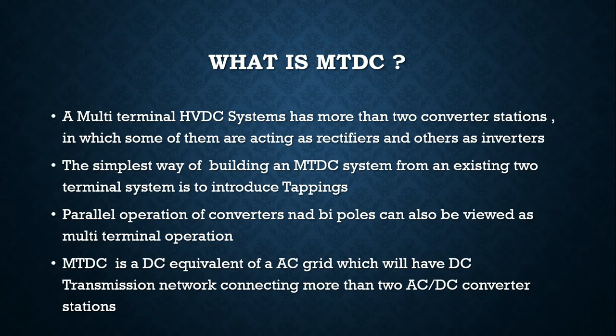A multi-terminal HVDC system has more than two converter stations, in which some of them are acting as rectifiers and others as inverters. The simplest way of building an MTDC system from an existing two terminal system is to introduce tappings. Parallel operation of converters and bipoles can also be viewed as multi-terminal operation. MTDC is a DC equivalent of an AC grid, which will have a DC transmission network connecting more than two AC/DC converter stations.